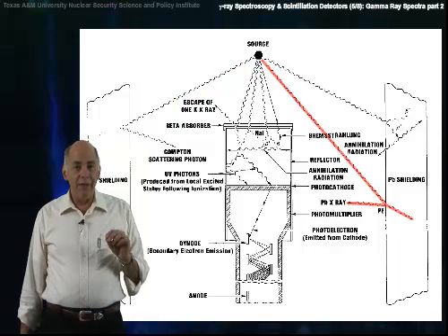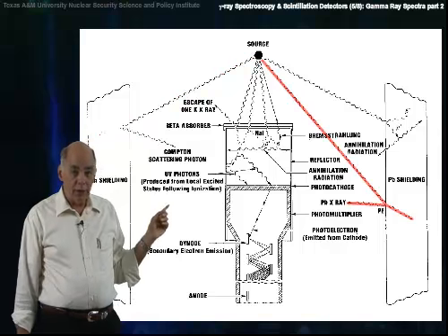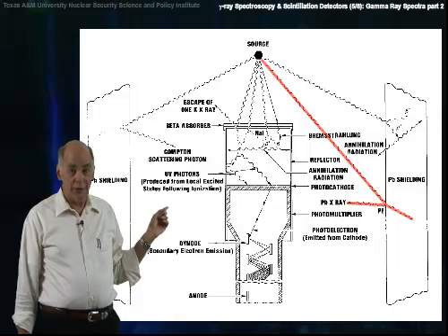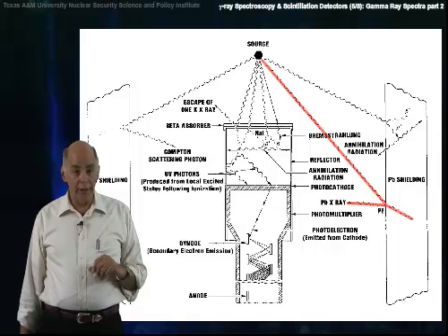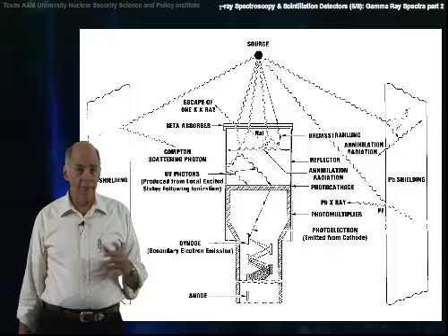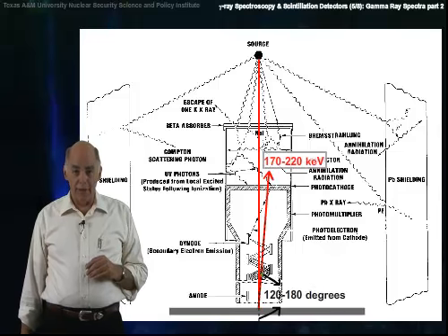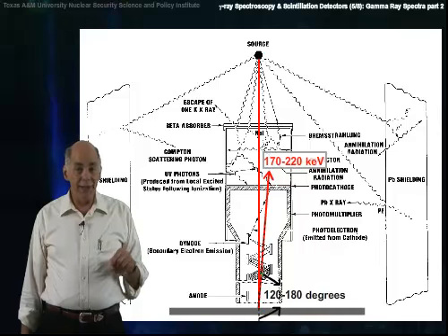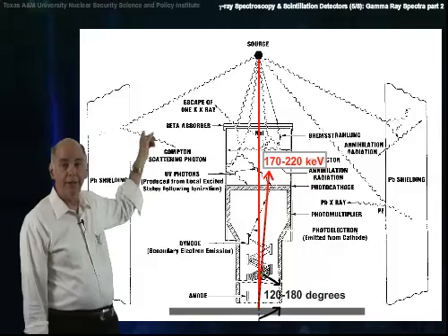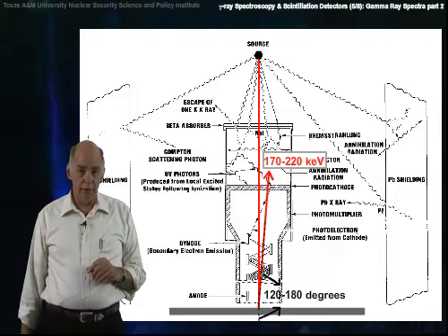With any gamma interacting in the shielding, lead characteristic X-rays will be produced. These can also enter the detector, and again, they're not part of the source spectrum. And finally, there are backscatter effects. If scattering material is present behind the detector, the returning gamma rays create a pseudo-peak.